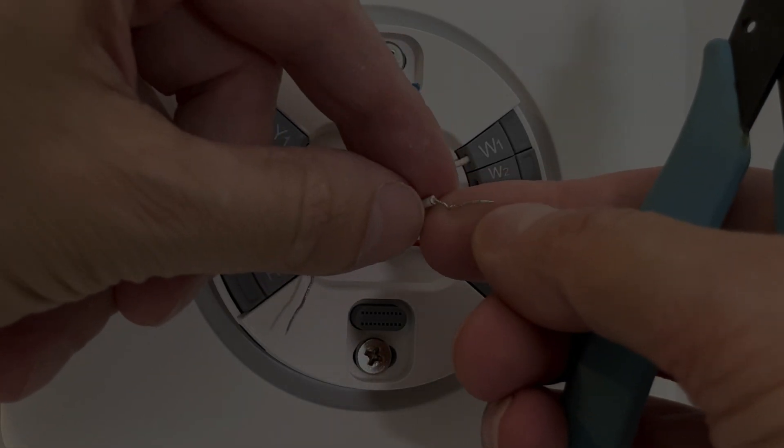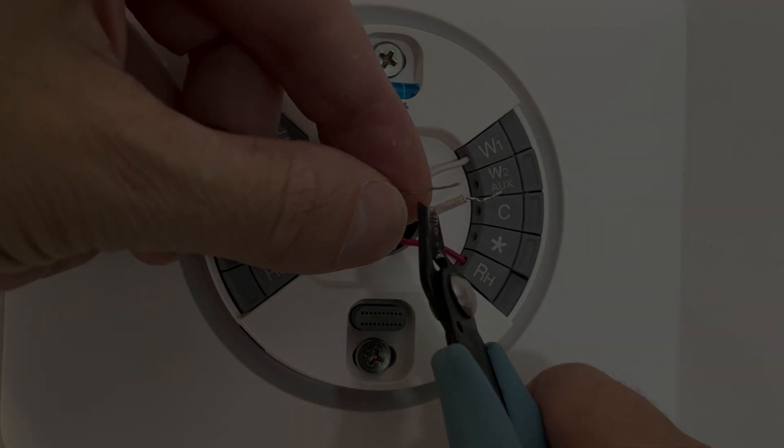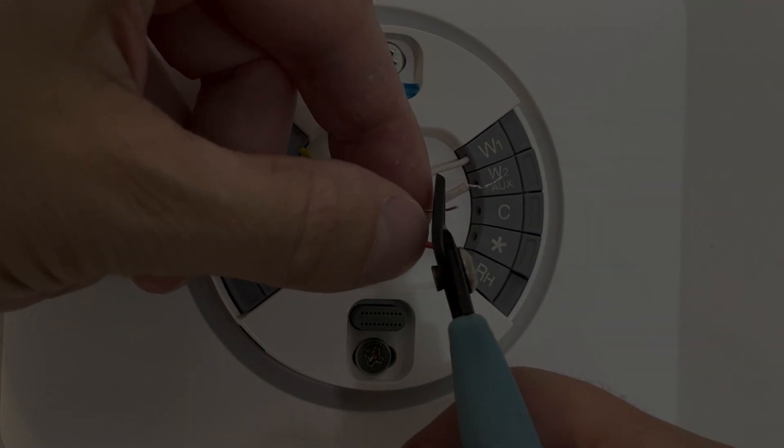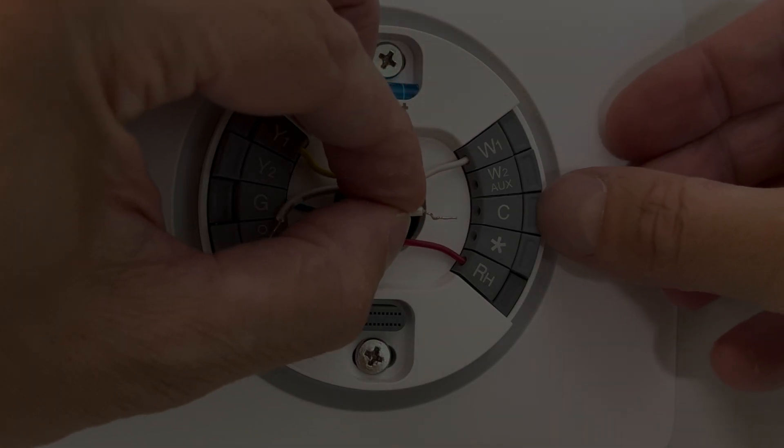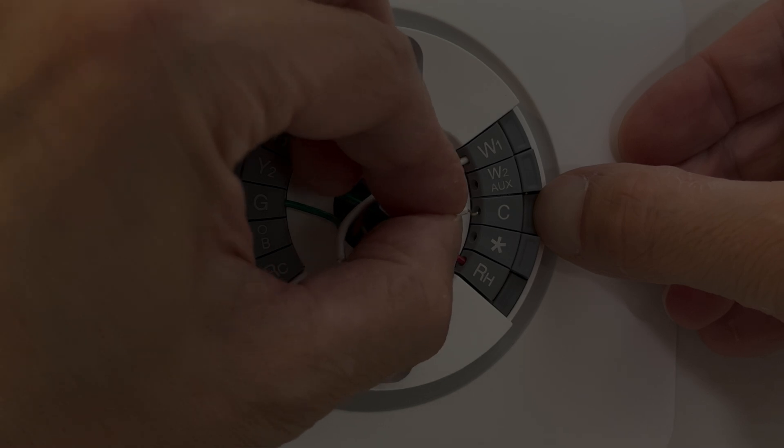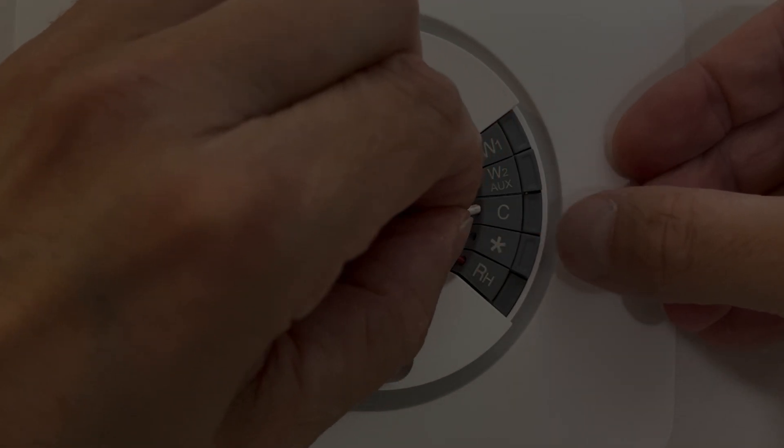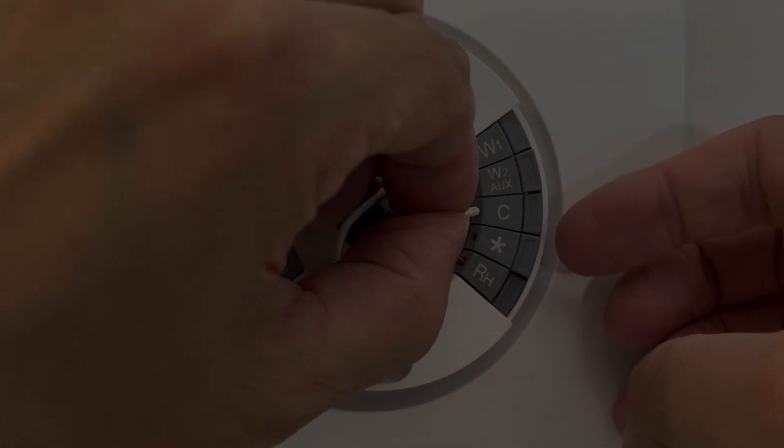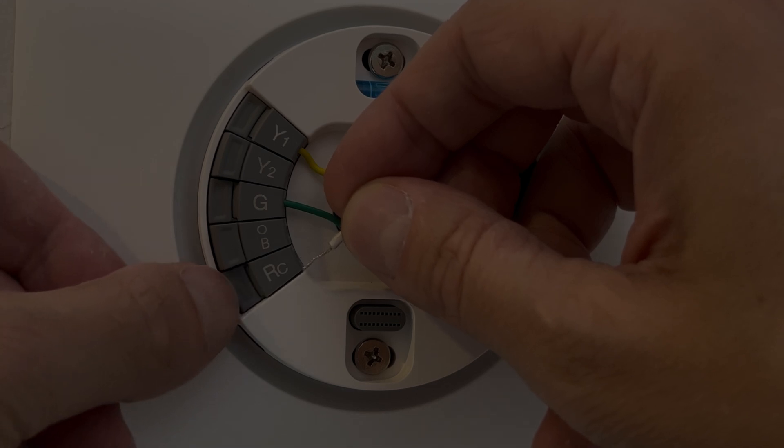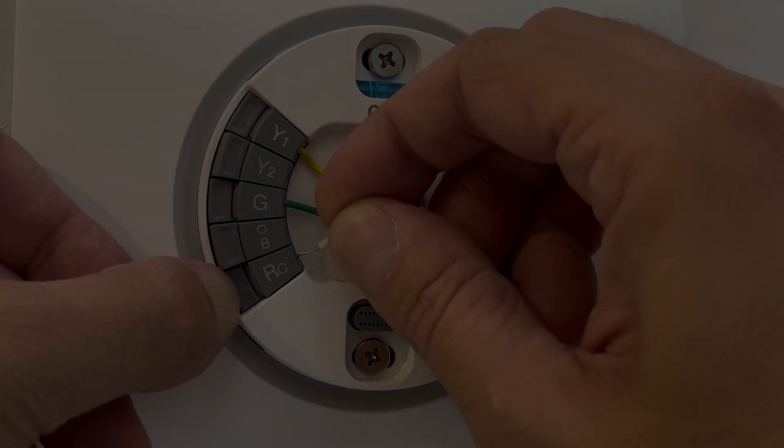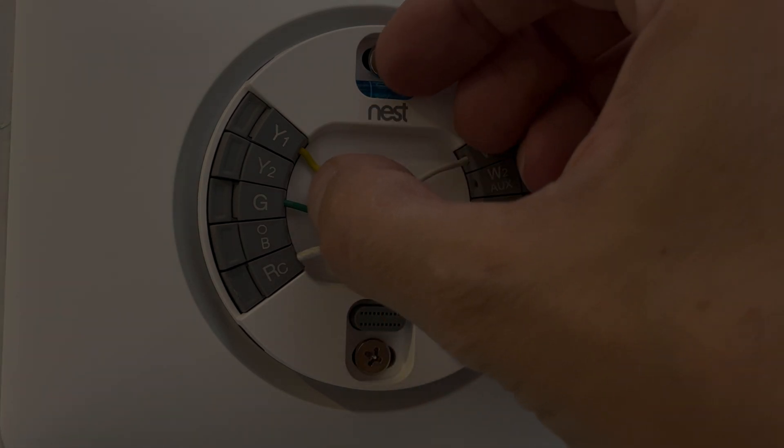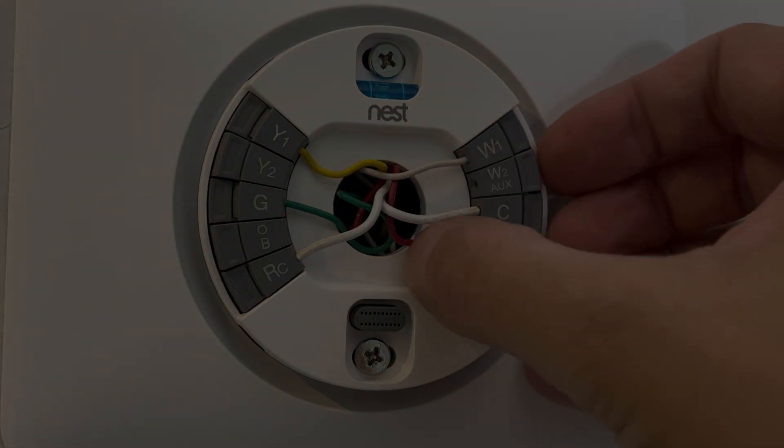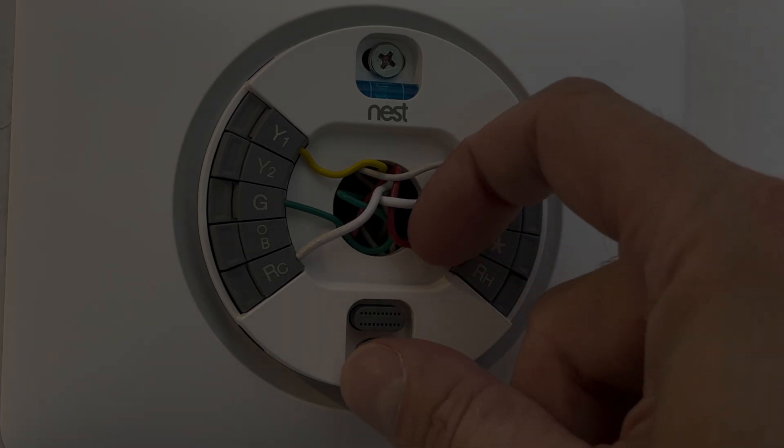So then we're going to take care of our two wires that we have here. It's alternating current so it does not matter which cable or which of the wires you use for what side right now. I'm going to clip this here to about a quarter inch of exposed wire. Then the first one, the first wire we're going to put here into the C slot. So we're going to press on that button on the outside of the ring and then we can push that wire right in there. Then we want to check and pull it just a little bit making sure that it doesn't become loose again. And we're going to do the same thing with the RC side as well, making sure that it does not come loose.